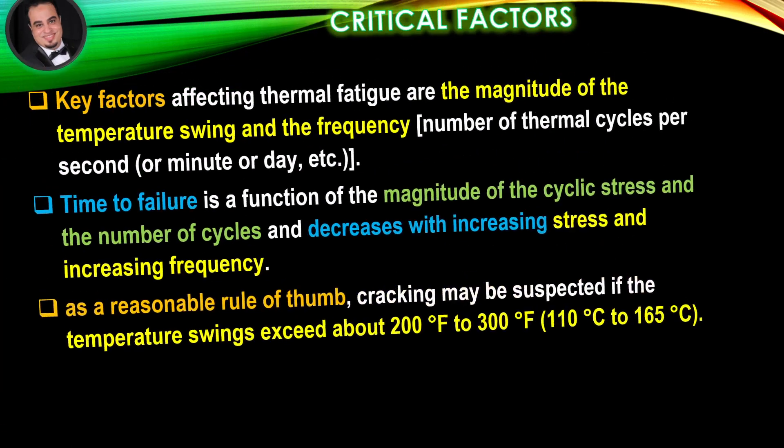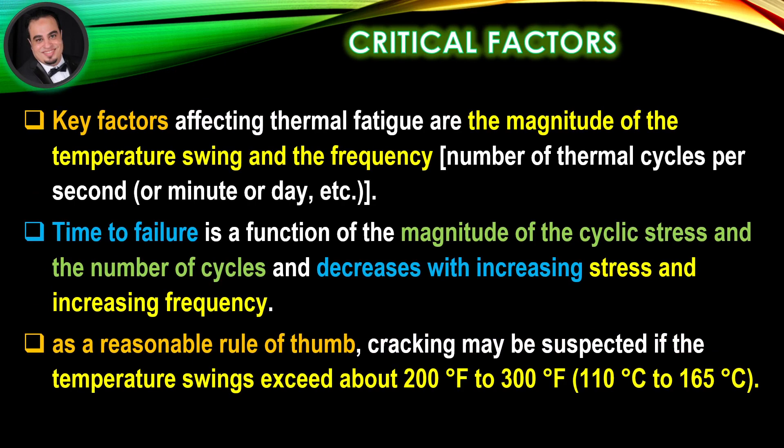Affected materials: all materials of construction. Key factors affecting thermal fatigue are the magnitude of the temperature swing and the frequency — number of thermal cycles per second, minute, or day. Time to failure is a function of the magnitude of the cyclic stress and the number of cycles, and decreases with increasing stress and increasing frequency. As a reasonable rule of thumb, cracking may be suspected if the temperature swings exceed about 200°F to 300°F.